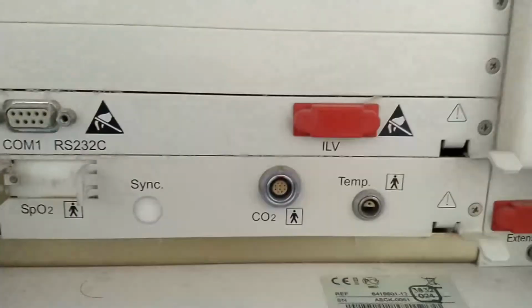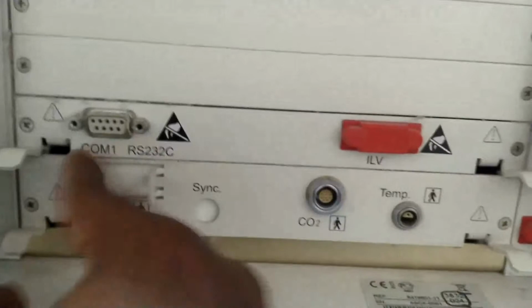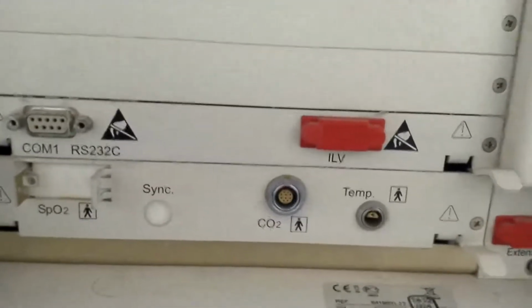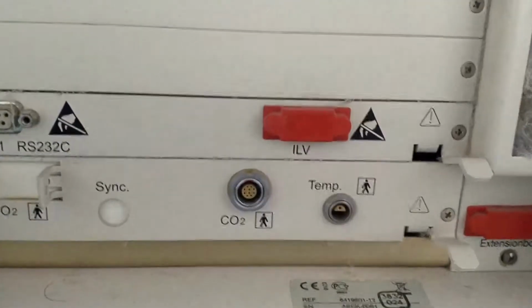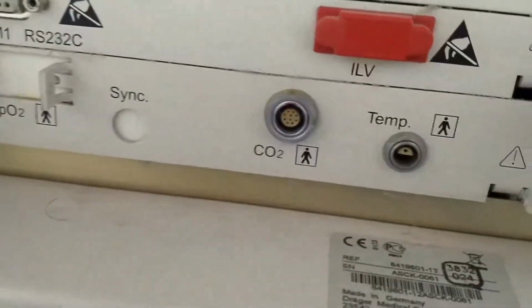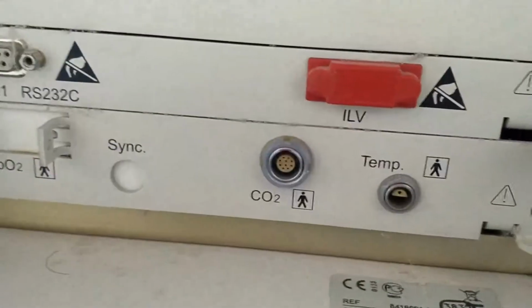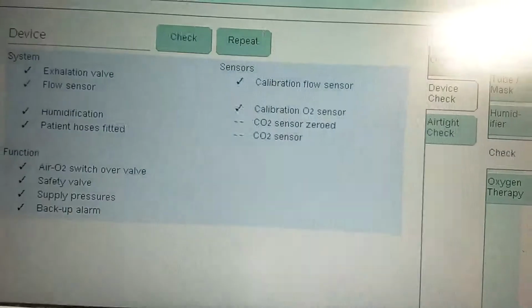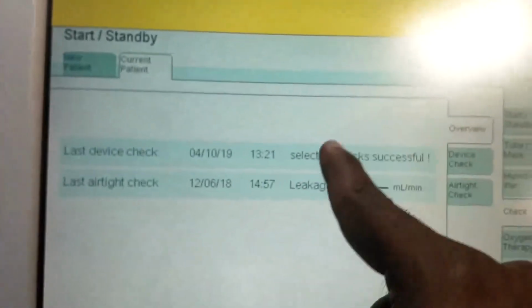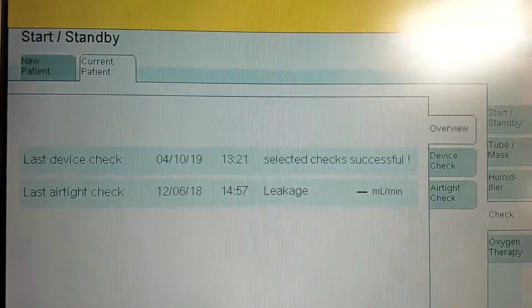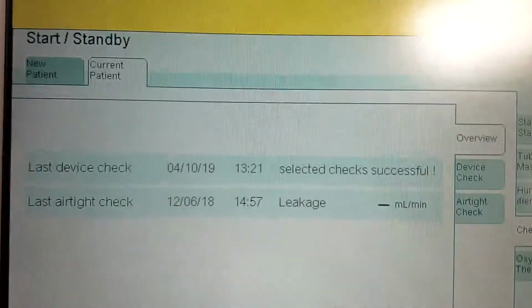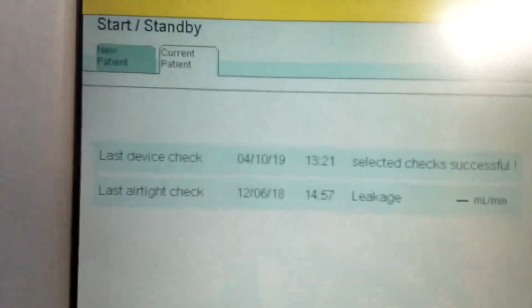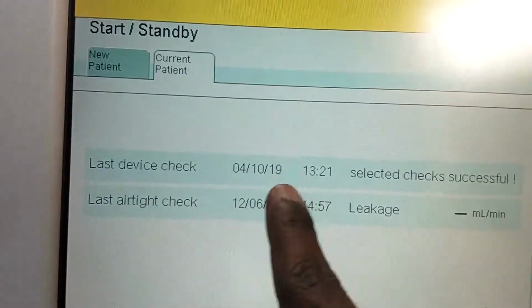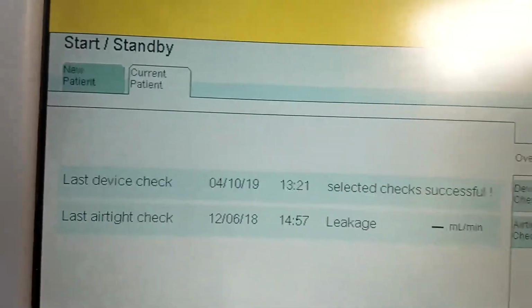So the CO2 sensor is not connected, and a temperature sensor can also be connected. The air temperature and the CO2 end tidal carbon dioxide sensors are removed. That's the reason why these two tests are skipped. Otherwise all the other tests passed. So it says selected checks successful. Out of the device check, most of the checks are successful. And it says when we did the test, it's 10/4/2019, 1:21, we have completed the test. Okay.